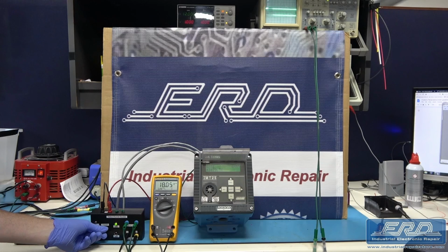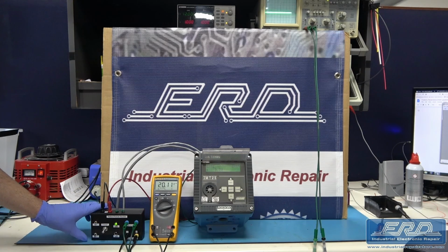As you can see in the video, a simulated flow meter magnetic signal is applied to the converter, and then the proportional 4-20 mA output is monitored for proper operation and scaling.